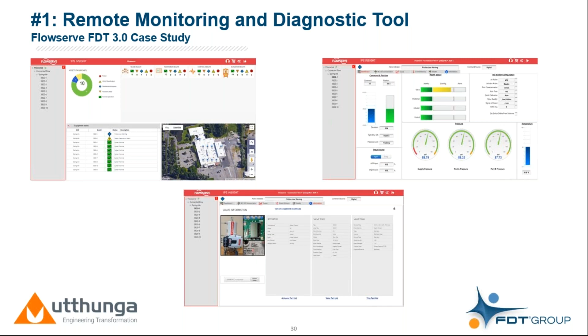When you find this NAMUR health status information, you can also go a little deeper. It's not just saying the device is not working, but you can also see information related to the device, the reason for the issue, and how to provide remedies for it. This category is not only for remote monitoring, but also supports device commissioning, calibration, and diagnostic information via the FDT server.